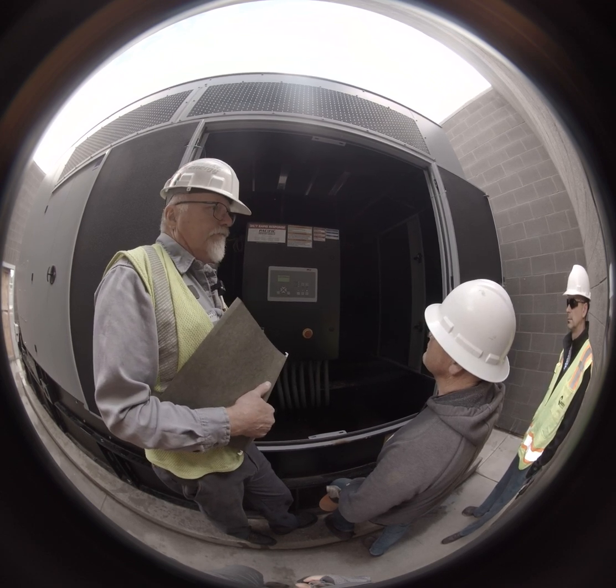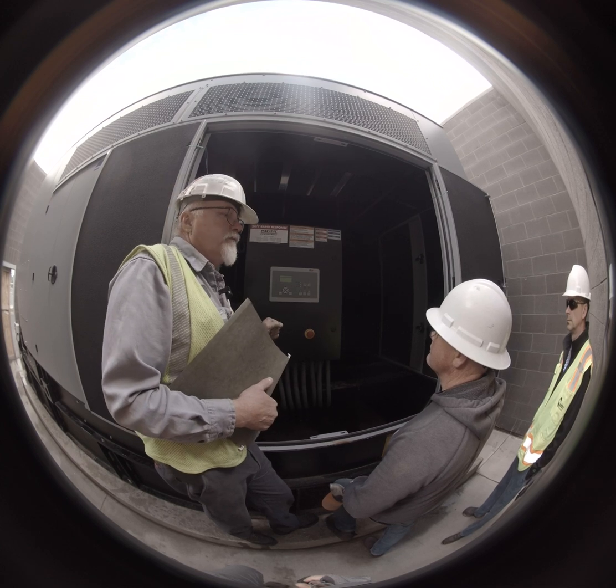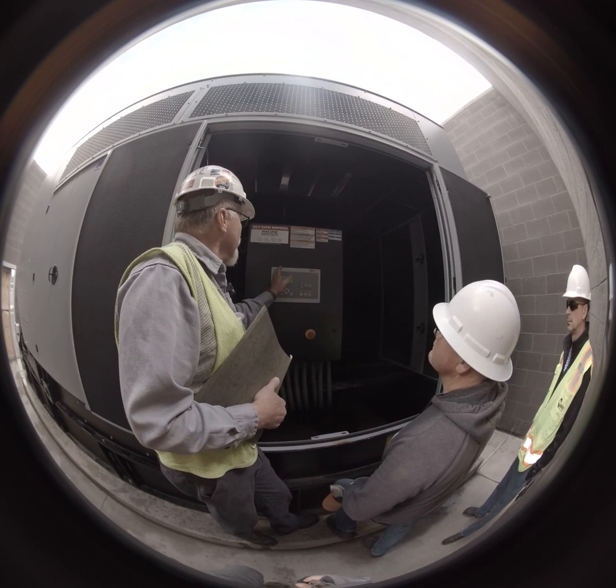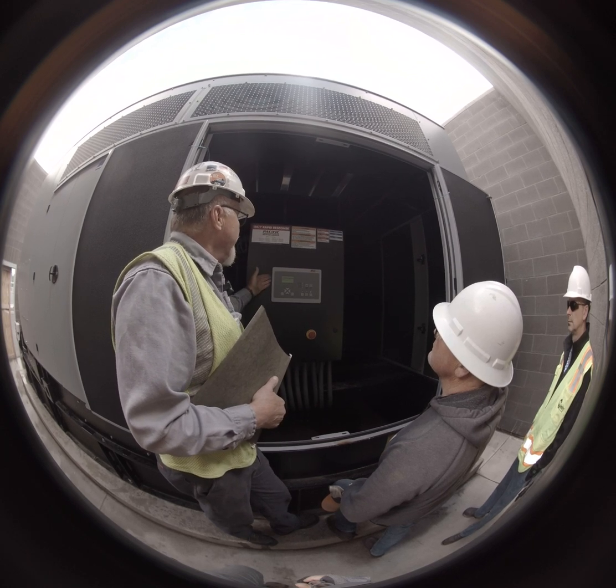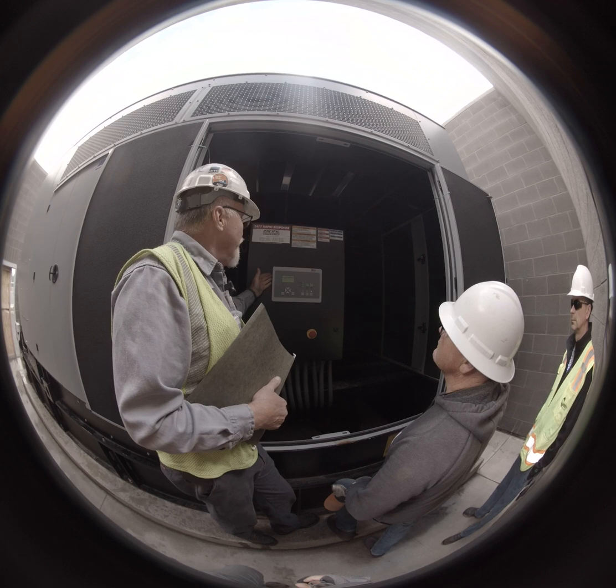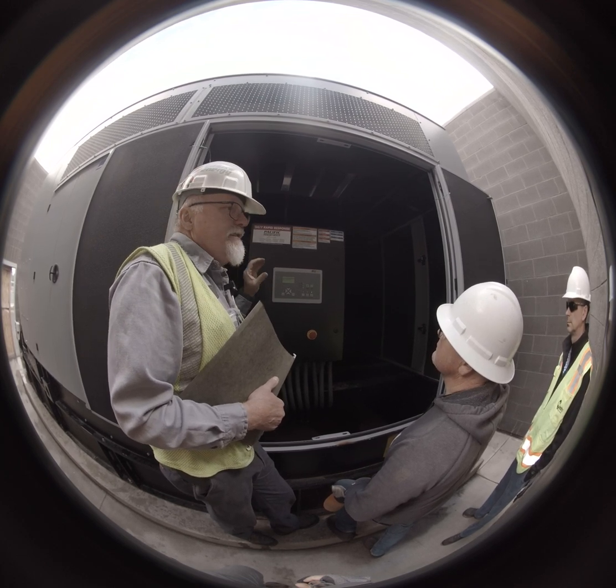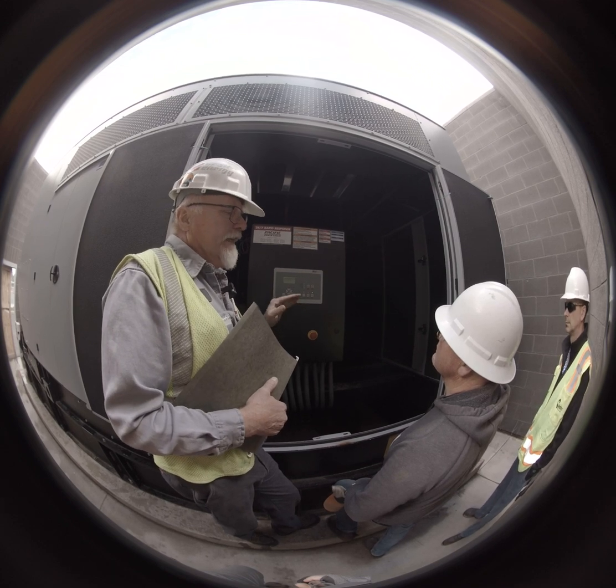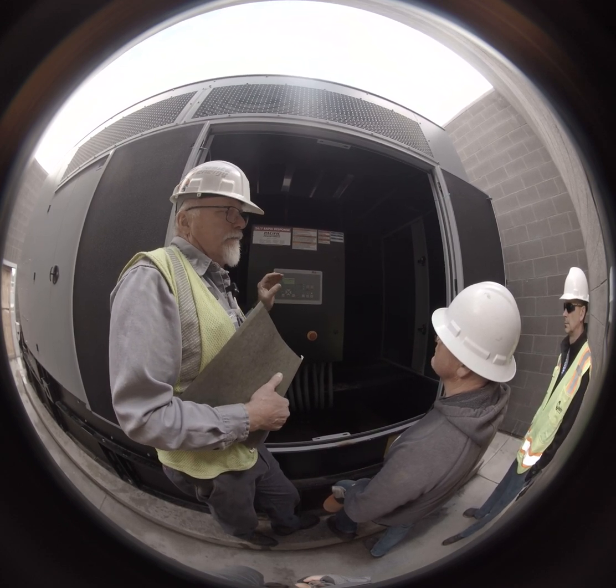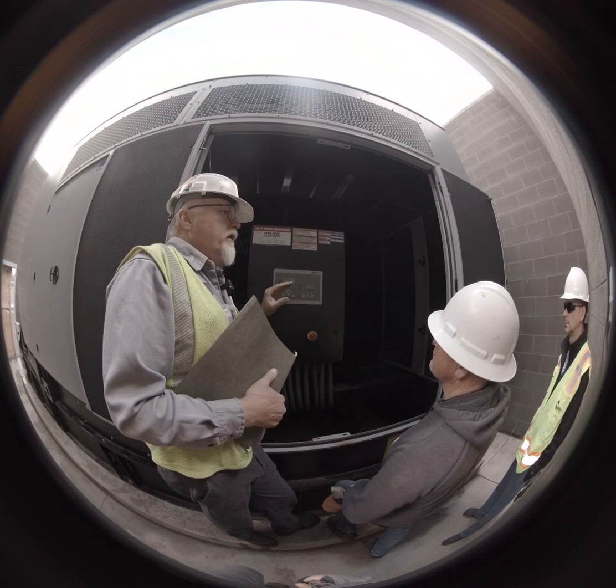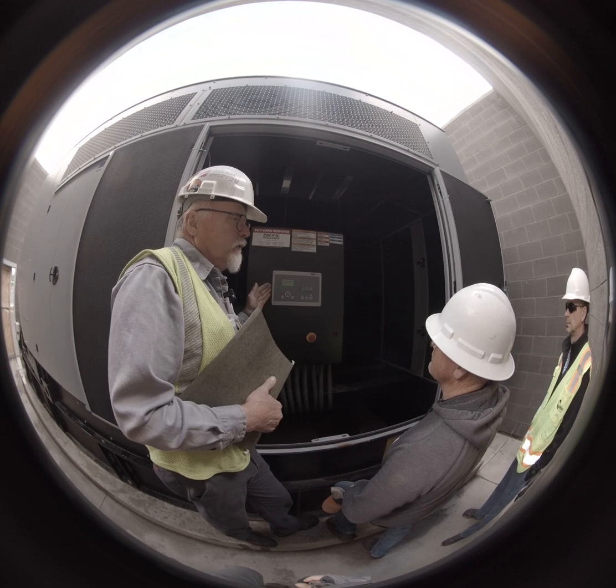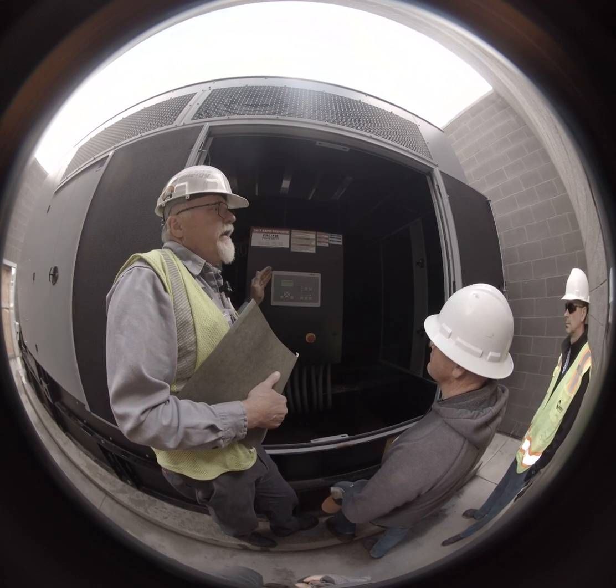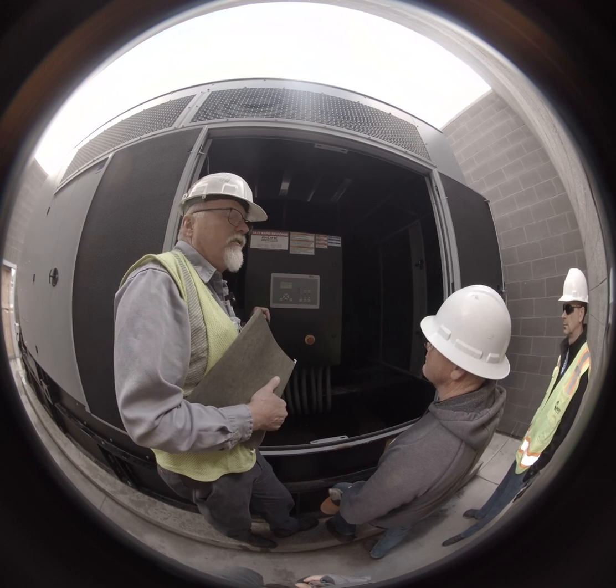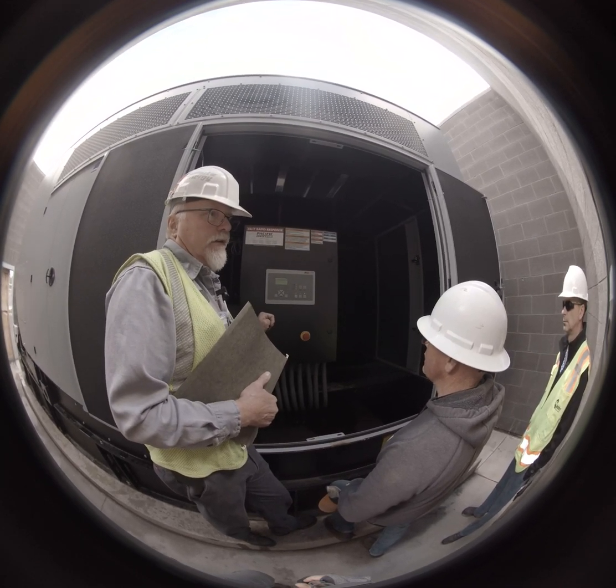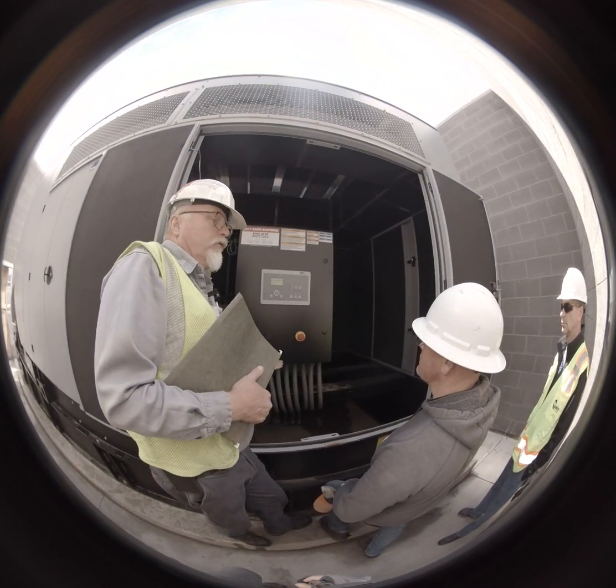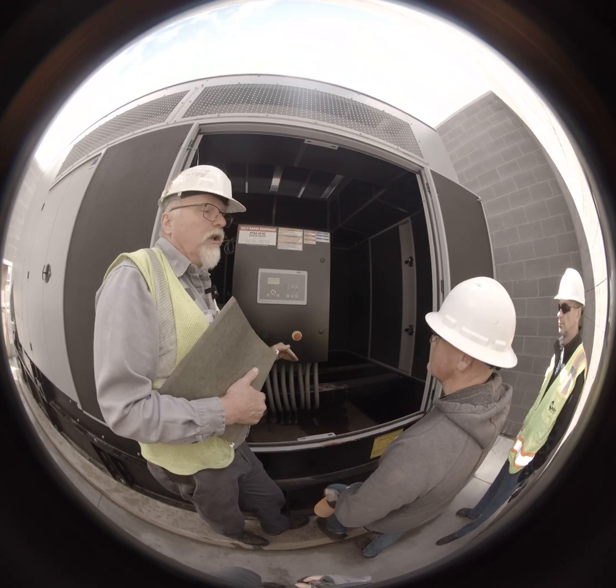You've got cumulative. Cumulative is the total from the time this machine was commissioned. Actually, two levels there and then three within. Under cumulative, you have the total runtime, how much of that was with load, and how much was unloaded. The difference between loaded and unloaded is quite simply the current ratio. So if we have a current transformer in this generator set, which is probably a 600 to 5, if it hits over 3% of 600, then it will say that it actually is running with a load. So it doesn't necessarily say you're at 50% load or 25% load or anything like that. It just tells you that, yes, it had a load on it.